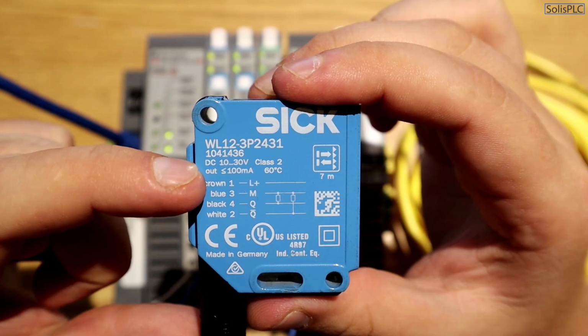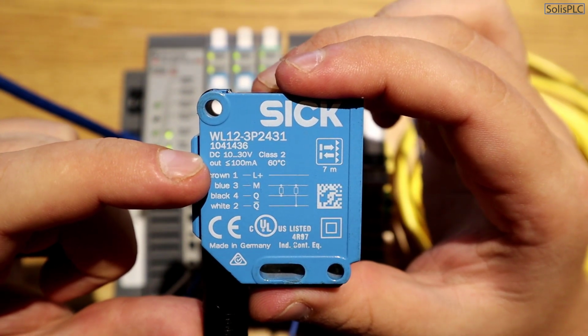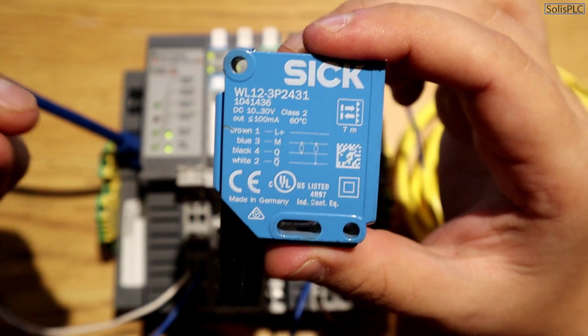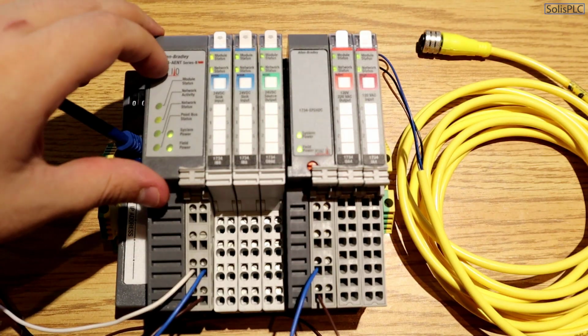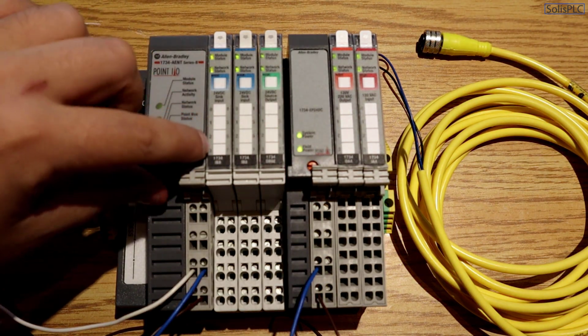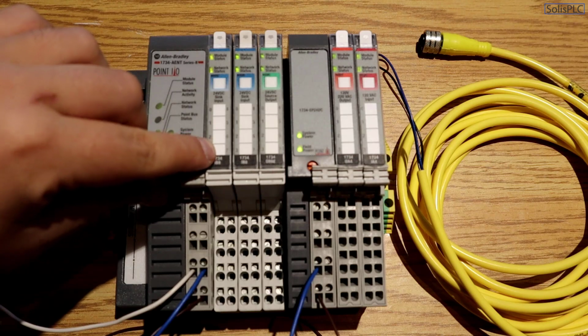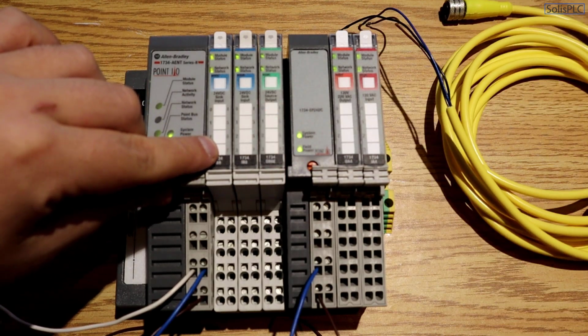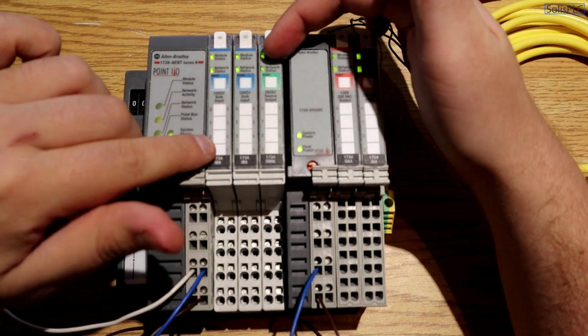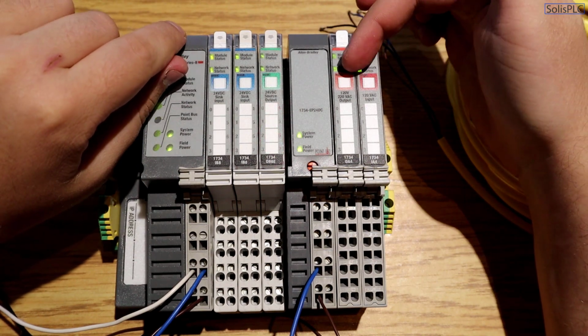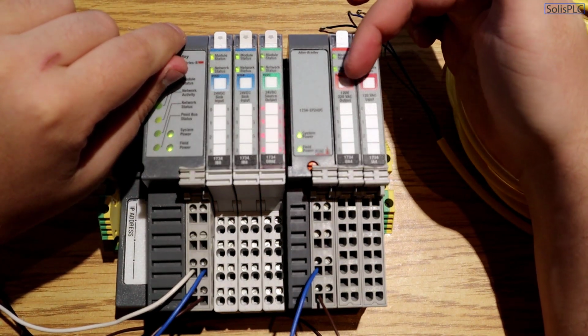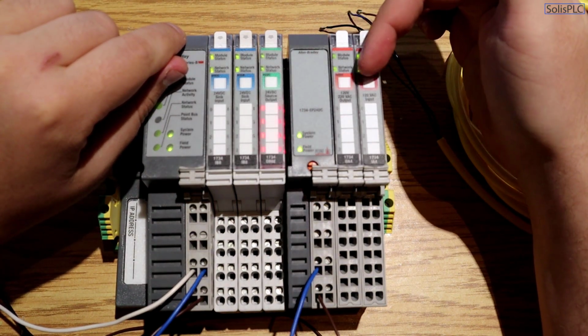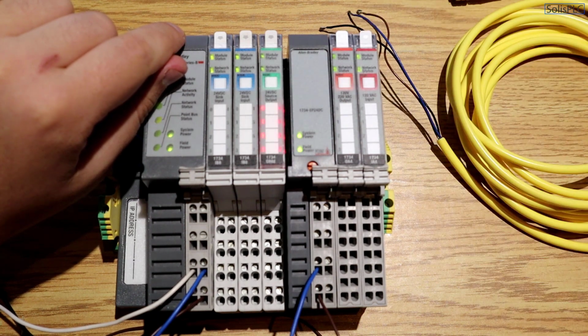As you can see here, it's a DC 10 to 30 volts class 2 sensor. Essentially that indicates to us that it needs to be mated to this input card. The first two cards are input cards on the 24 volts side. If you were to plug it into the output, of course, the sensor is not going to do anything. And if you plug it into any of the 110 VAC cards, you risk damaging the sensor.